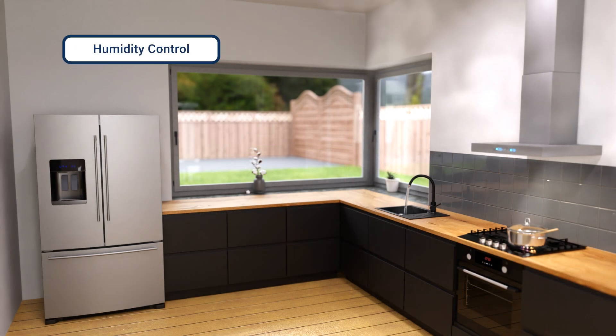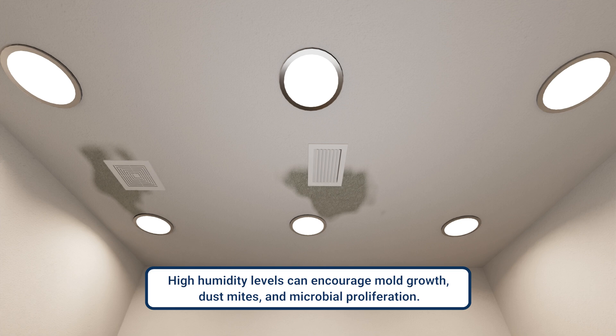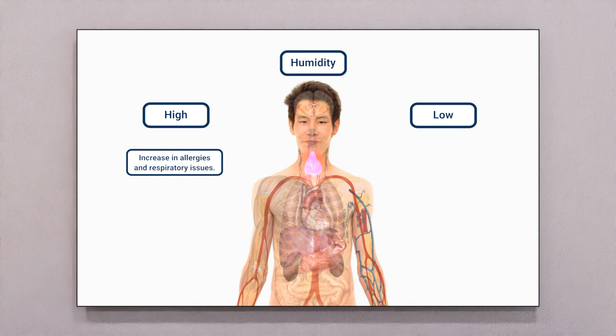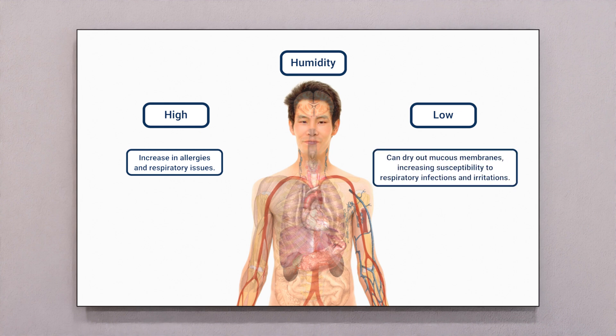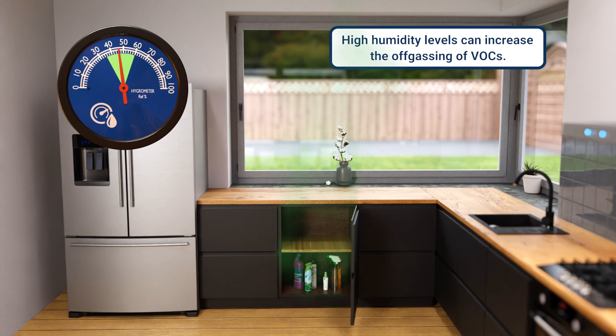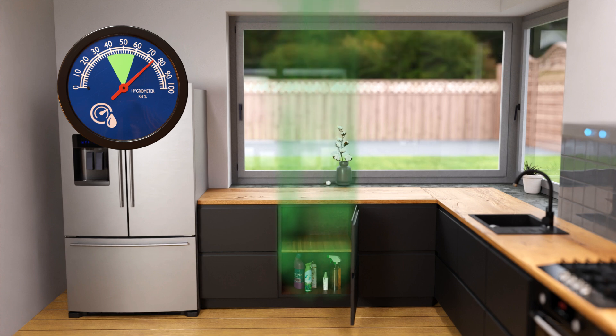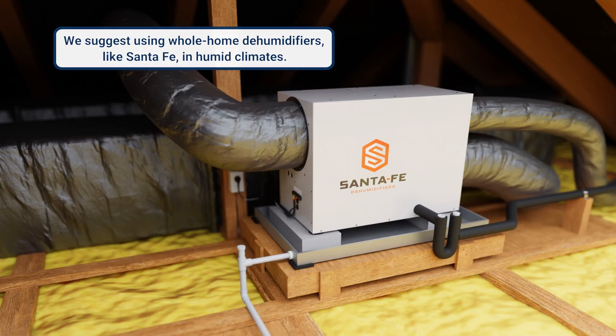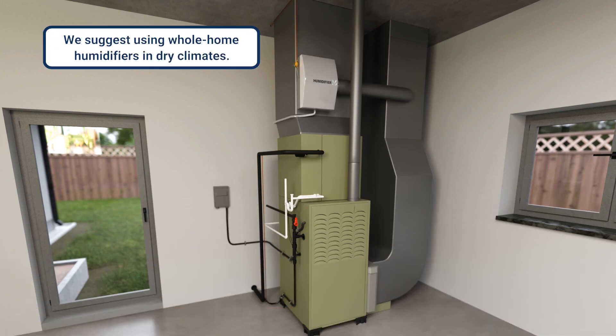Humidity control: High humidity levels can encourage mold growth, dust mites, and other microbial proliferation, causing an increase in allergies and respiratory issues. Low humidity can dry out mucous membranes, increasing susceptibility to respiratory infections and irritations. The ideal indoor humidity range is between 35% and 60% relative humidity. High humidity levels can also increase the off-gassing of VOCs. We suggest using whole-home dehumidifiers like Santa Fe in humid climates, and whole-home humidifiers in dry climates, properly installed by a professional in conjunction with the existing HVAC equipment.